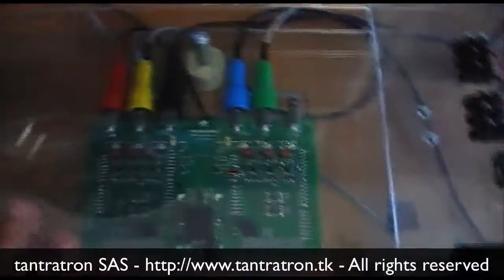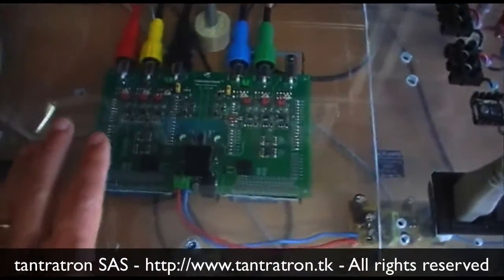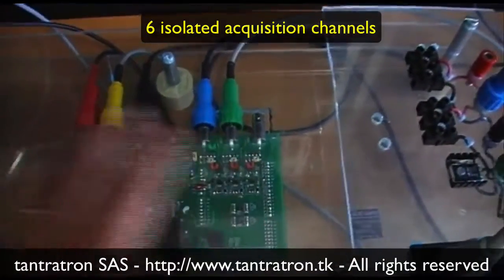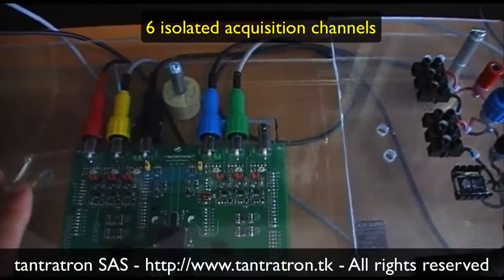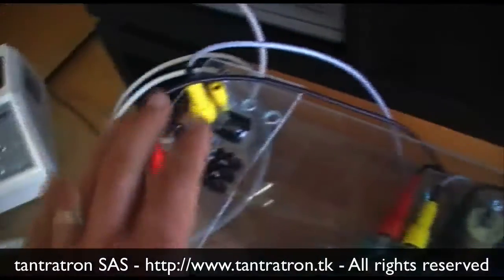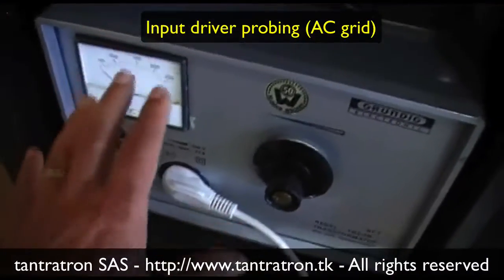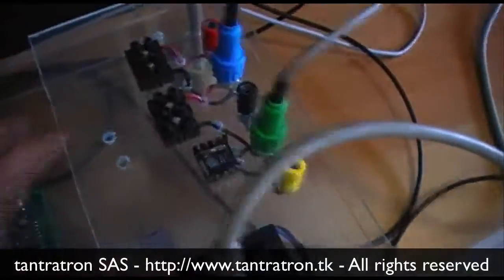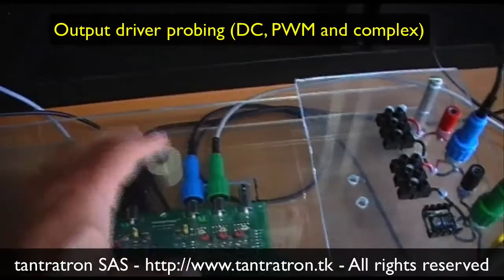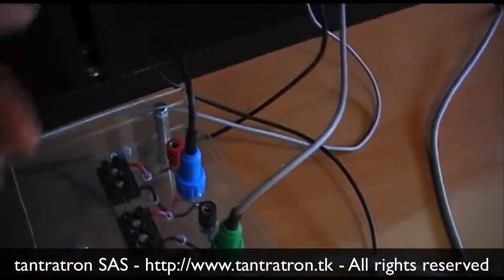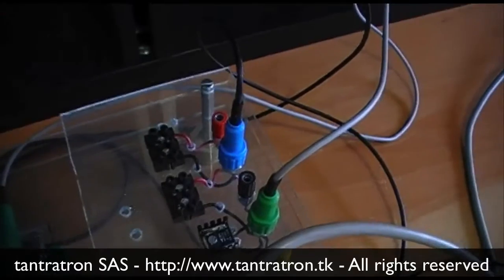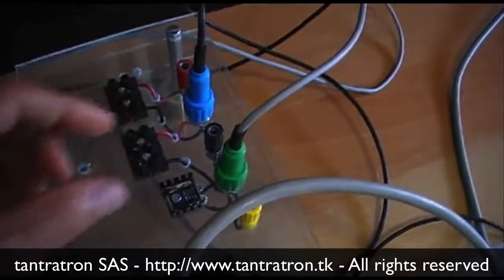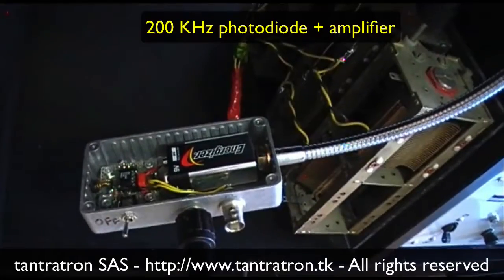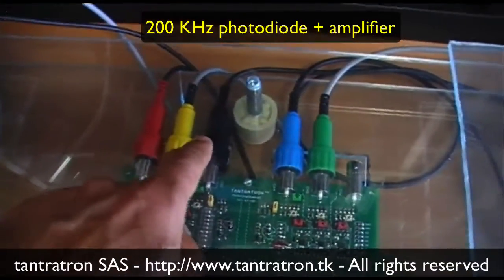Okay, so on the hardware part you've got 6 isolated independent acquisition channels. 3 of them are dedicated to the input grids, and as you know, you can change the grid voltage. You've got a current probe and a voltage probe, and again you get the same thing, except in between you get the LED driver or the LED ballast, and here is the output, which would then be connected to the LED chip. So again, current probe and so on. And you've got a very fast photodiode with its amplifier, which for example is triggering here.